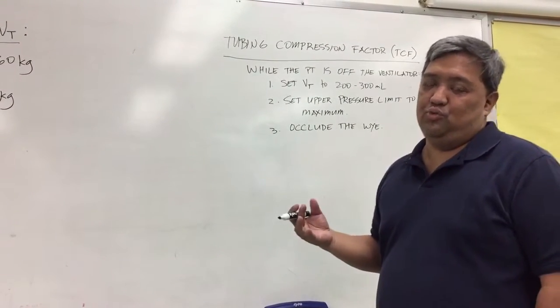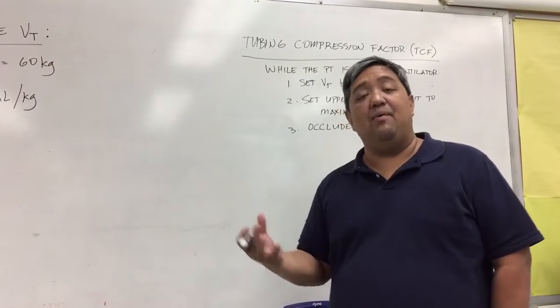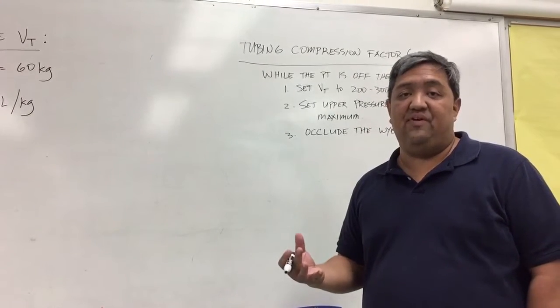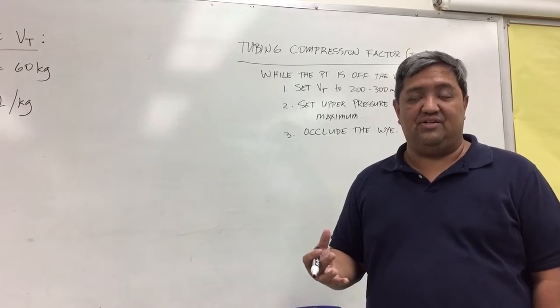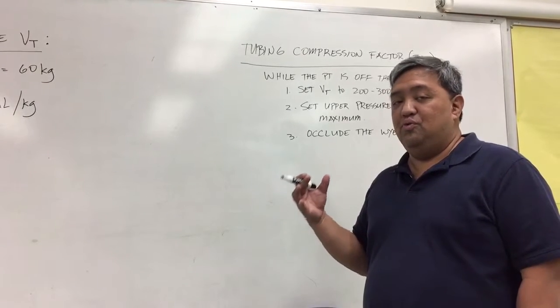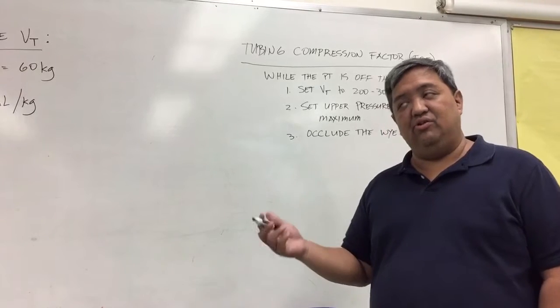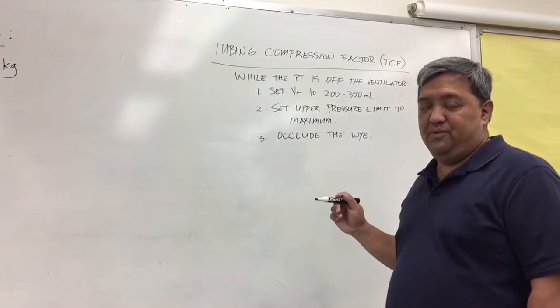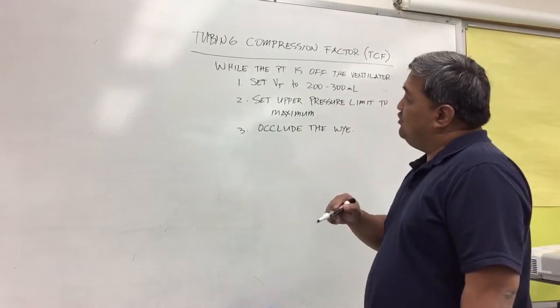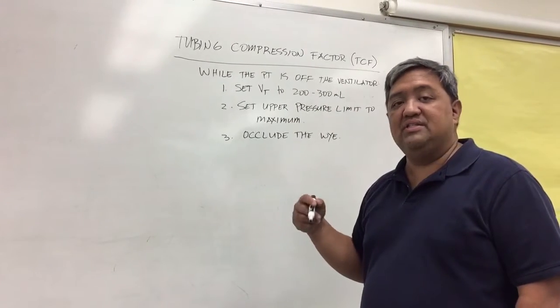Some of the ventilators, especially the older ones, don't compensate for tubing compressibility factor or tubing compensation factor. In order to know the actual volume being delivered to the patient on older ventilators, we need to know the tubing compressibility factor. To do that, while the patient is off the ventilator...